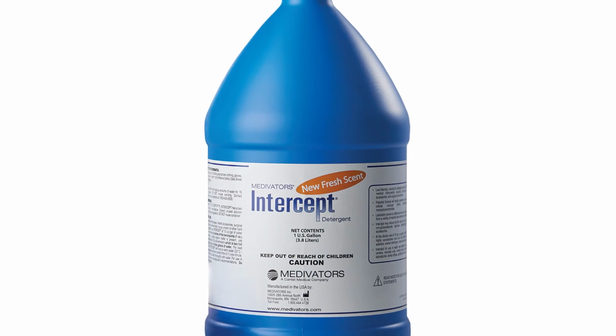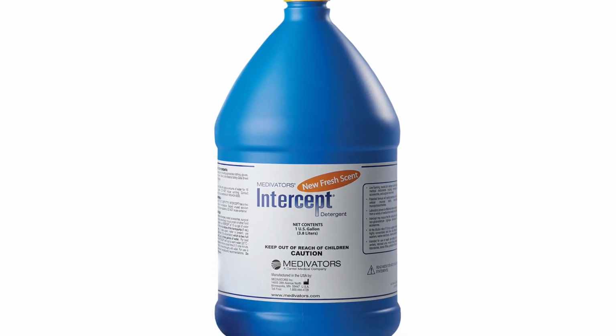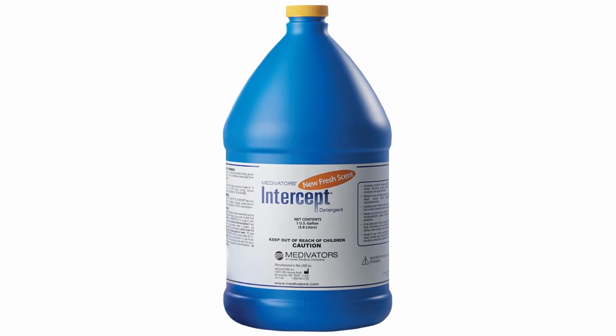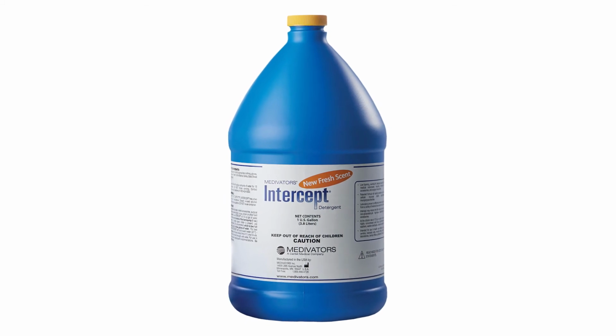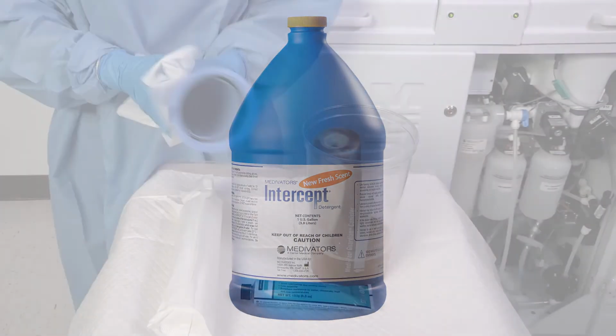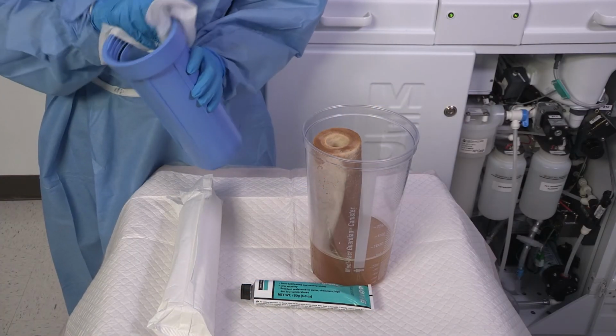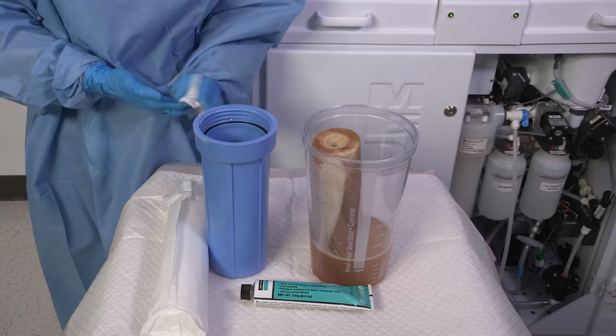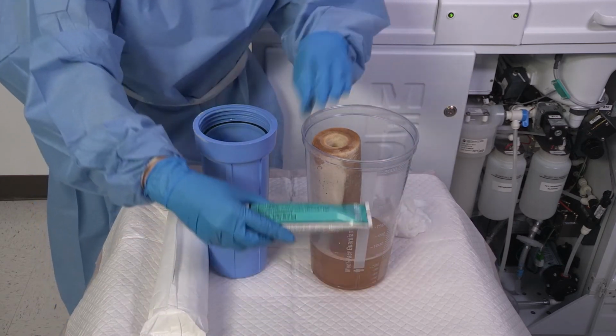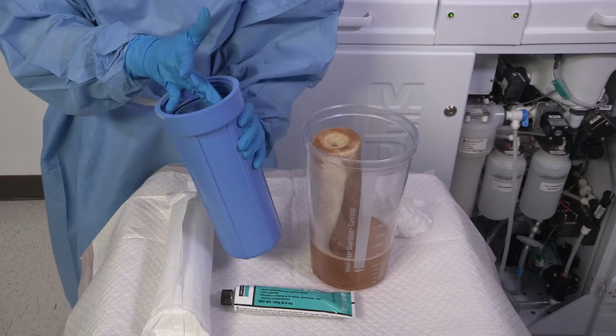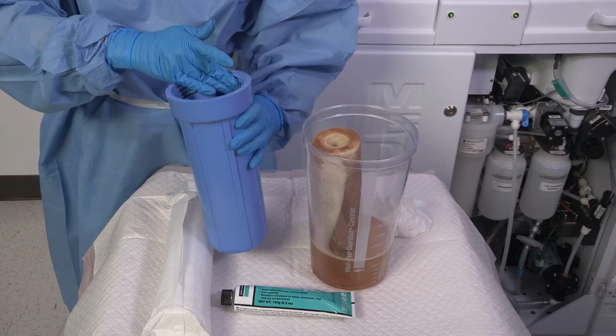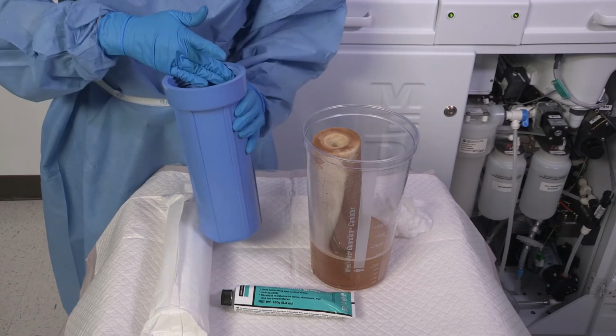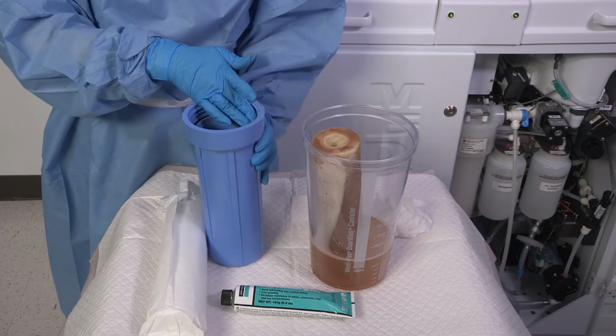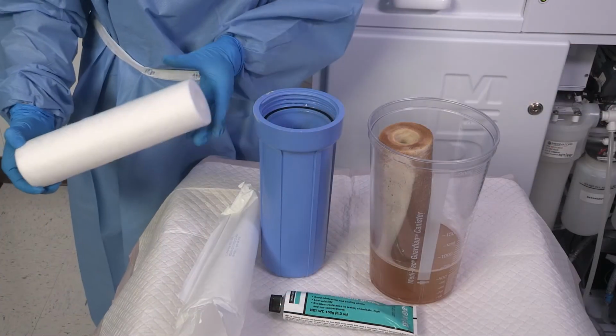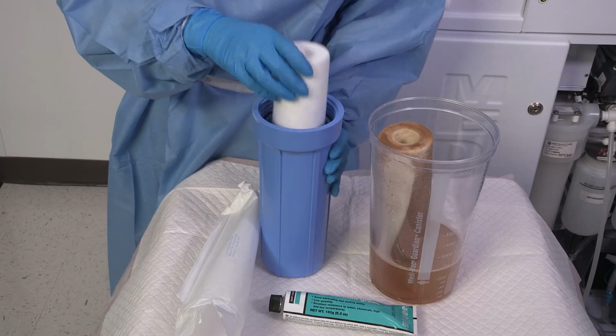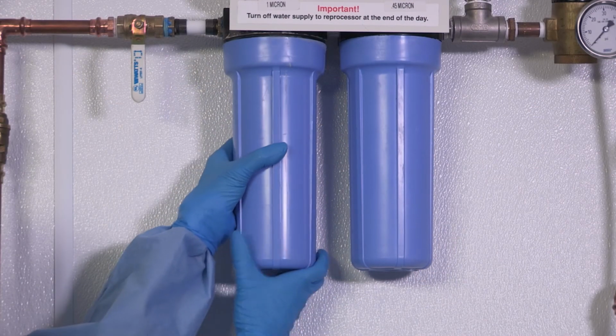The filter housings can be cleaned by washing with neutral pH, low-foaming, medical-grade detergent, such as Intercept detergent, then rinse thoroughly. Inspect the O-ring inside the housings for twists, wear, or damage. Replace if needed. Apply high vacuum grease to the housing's O-ring and threads if needed to aid in installation and sealing. Place a new 1 micron filter inside the filter housing and reattach.